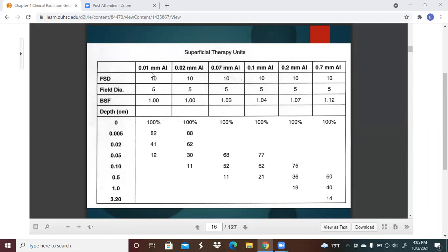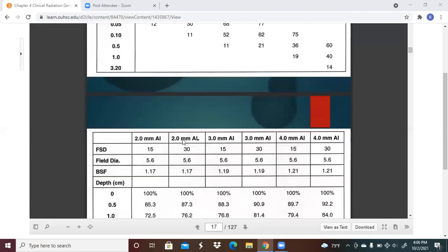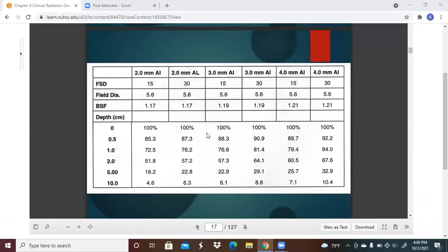So you can see here that you've got a 100th of a millimeter of aluminum, and you can see that all of these have a depth of 100% right on the surface. You don't have to go very far in order to see this thing start to degrade. Just watch the beam degrade. And it's not that much of an increase in the amount of aluminum there. Same thing here. Got something with 2 millimeters of aluminum up to 4 millimeters of aluminum, depending on your focus to surface distance. And you can see the depths, and you can see that at least here in this particular range, you can start to see where you still have some remaining dose going deeper into the patient.